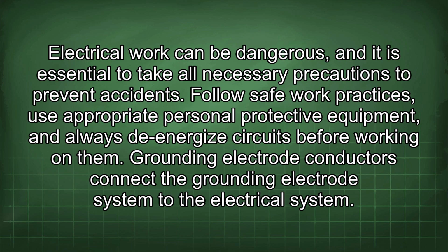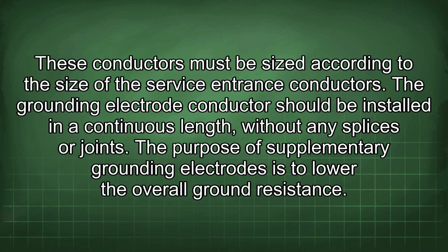Grounding electrode conductors connect the grounding electrode system to the electrical system. These conductors must be sized according to the size of the service entrance conductors. The grounding electrode conductor should be installed in a continuous length, without any splices or joints.